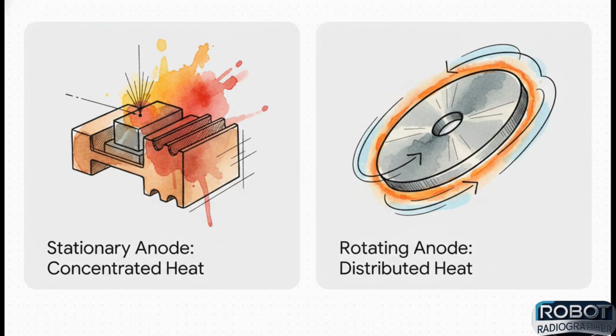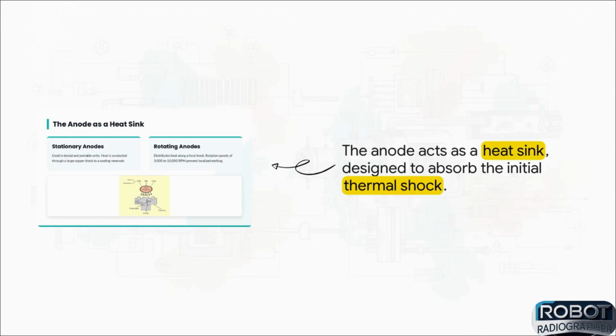The solution? A truly brilliant innovation, the rotating anode. This thing spins at insane speeds. We're talking up to 10,000 RPM. So the beam of electrons hits a constantly moving target. It spreads that intense heat over a much bigger area, and that's what prevents a total meltdown. So really, the whole anode is basically designed as a heat sink. Its entire purpose is to absorb that initial thermal shock before it has a chance to go anywhere else. Whether it's spinning or standing still, its number one job is to take the hit.